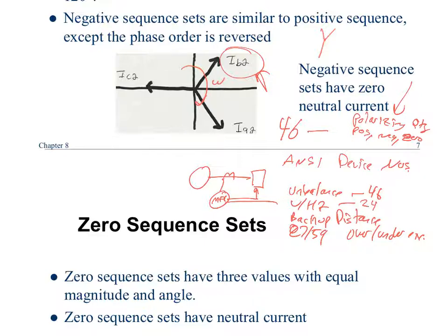That's a very important nugget for those of you who are going to be working, and I know a few of you are, working in the relay protection settings, why these terms are important, understanding the concept behind them. Because a lot of people say, well, why bother teaching it? Because CAPE, Aspen, all these programs, they don't actually use 0, positive, or negative sequence networks, but all the relays do. And that's what the protection is going to be for the foreseeable future based on these quantities. I don't see any change afoot to go away from that.